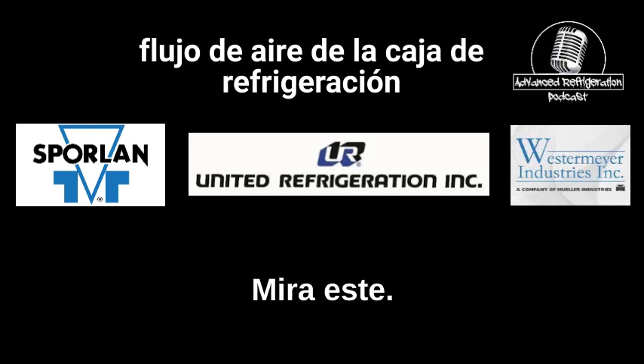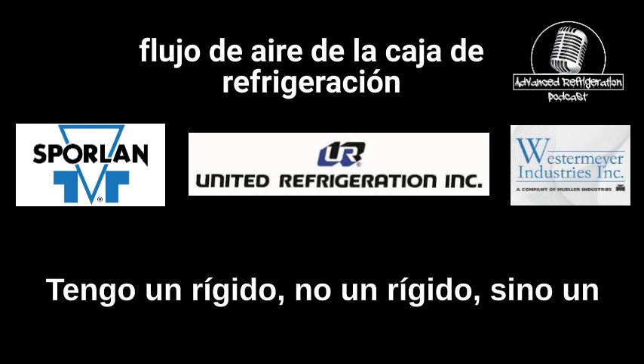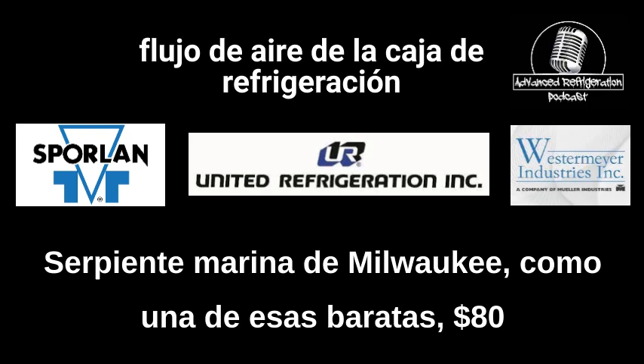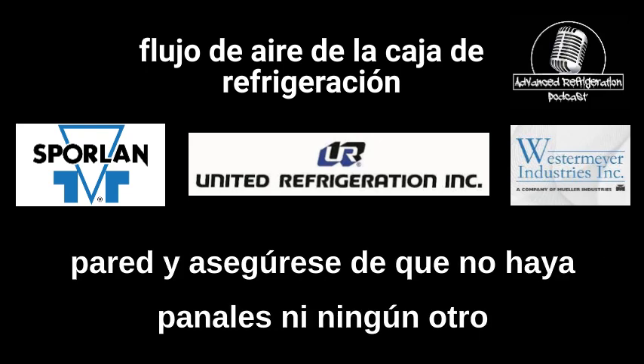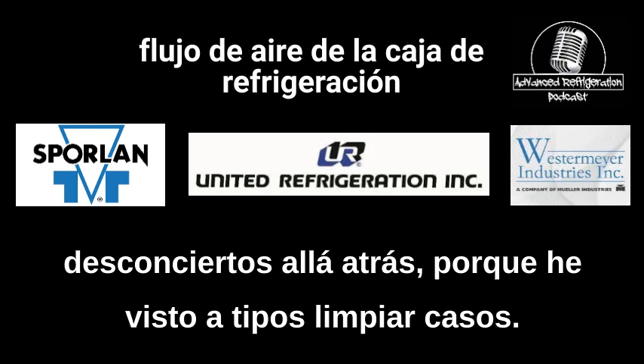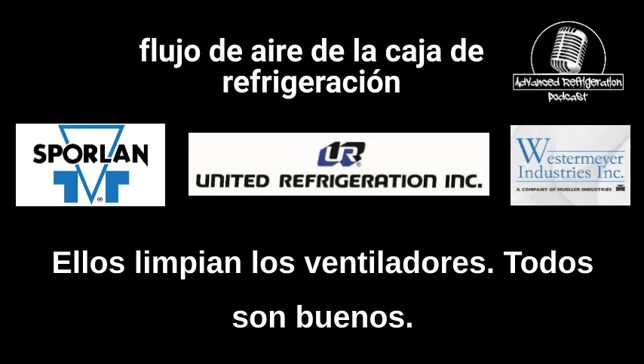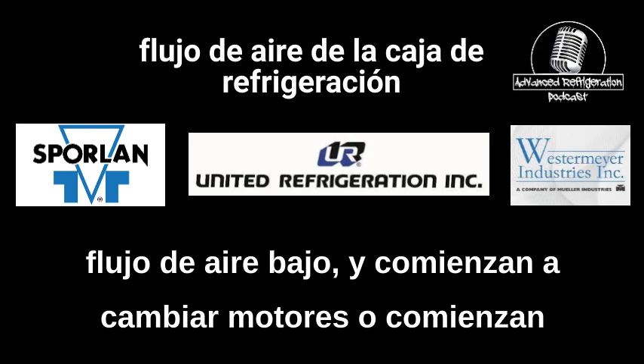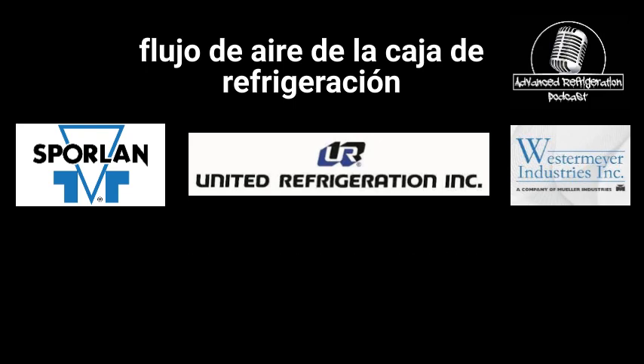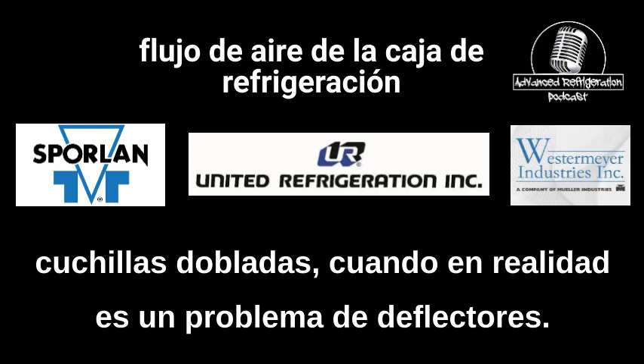Like, look at this, I have a Milwaukee Sea Snake, one of those cheap, like $80, flexible cameras. And I'll drop it down the back wall and make sure there's no honeycombs or any baffles back there. Because I've seen guys clean cases, they clean a coil, they clean the fans, they're all good. They clean the honeycombs, and they still have the low airflow. And then they start changing motors or bending blades when really it's a baffle issue.